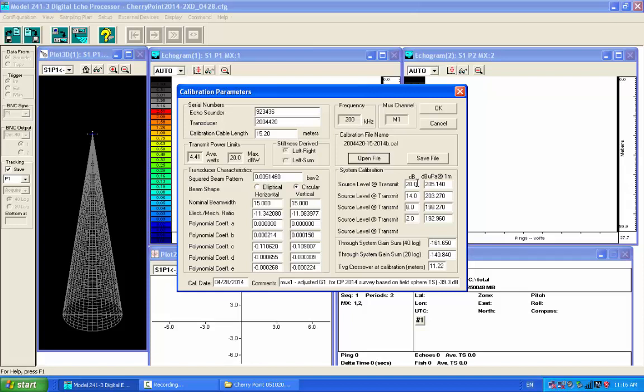I was just wondering if there was something like that, like we don't calibrate on the weekend when everybody's out. That's true. Our tech is usually the guy doing them, and he's pretty savvy. These have about a 6 meter separation between the test transducer and the others, so they're looking at relatively close ranges, and he can usually do a pretty good job of it. And then we always back these at the end with sphere measurements that need to check out against theoretical, just to give a benchmark going forward. So if he really was off, it would show there and he would redo it.